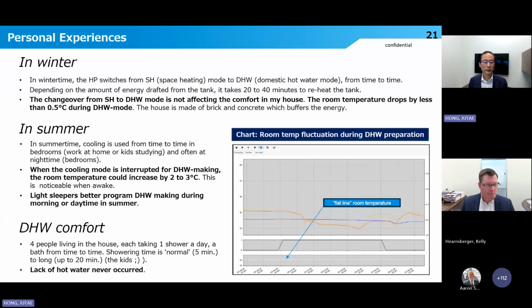We also have heard from our customers concerns about a drop in heating or cooling performance when using domestic hot water or any cases of hot water shortage. Here is the feedback from the homeowner. First, in winter, the changeover from space heating to domestic hot water mode is not affecting the comfort in the room. The room temperature drops by less than 0.5 Celsius during domestic hot water mode.